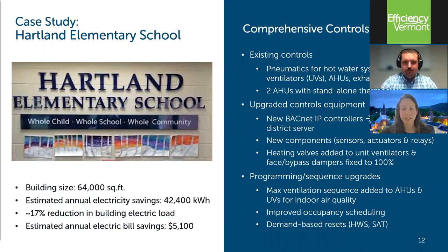As Nick mentioned, the improved scheduling and hot water supply temp reset sequences saved on electricity, but they likely also saved on fuel oil. But unfortunately, we didn't have access to that data in order to quantify the exact savings.